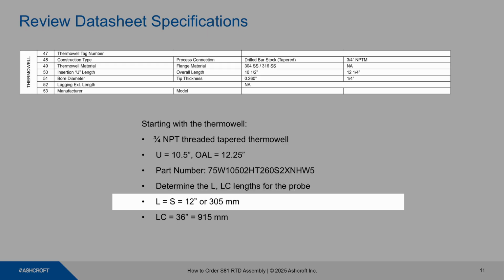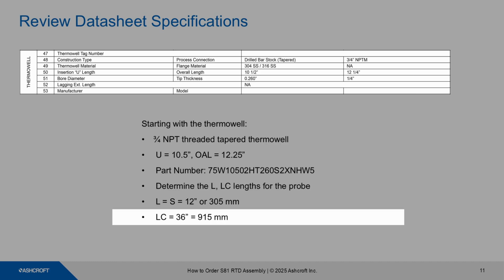Now we're going to determine the L and LC lengths for the RTD probe. The L is equal to the S dimension, which is equal to 12 inches, or 305 millimeters. The LC dimension is for 36 inches for the cable length, which is 915 millimeters.